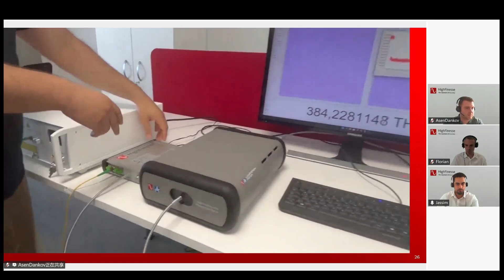In addition to this, you have the new casing, and then you have the connection to the computer. So let's maybe go to the connection. Your switch is connected to the wavelength meter via a LEMO cable, and this is simply connected to the wavelength meter from the TTL port on the backside, and your wavelength meter is connected via USB to the computer. And that's mostly it. This is most of the setup that you will need in order to start your measurement.